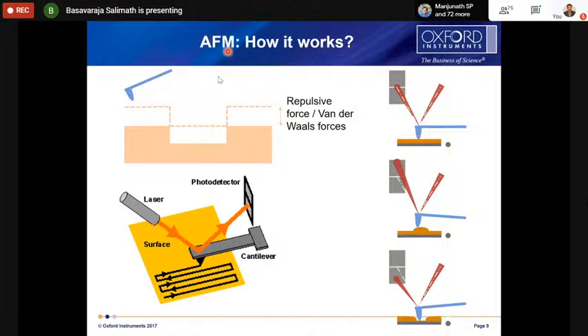But what we do in the AFM is we apply a little bit of force from the tip onto the sample. So by applying a little bit of force, we are entering into this repulsive force region. By keeping this force constant, we are now scanning laterally. When it goes to this place on the sample, you can see the repulsive forces are not there, so it is not experiencing these repulsive forces now. But it has to maintain the applied force, whatever the applied force was initially, constant while scanning. So that's why the tip will go down again.